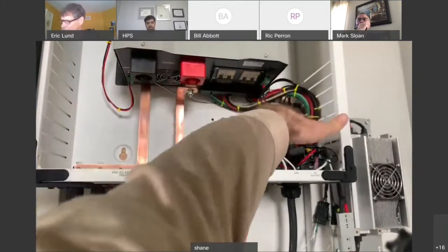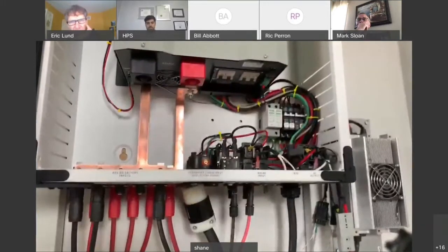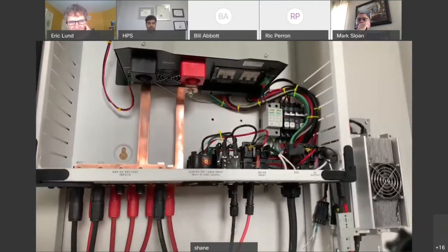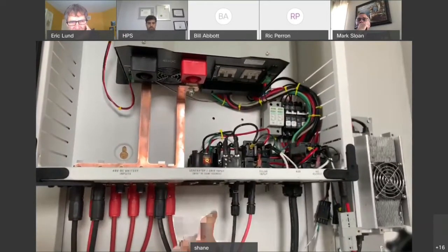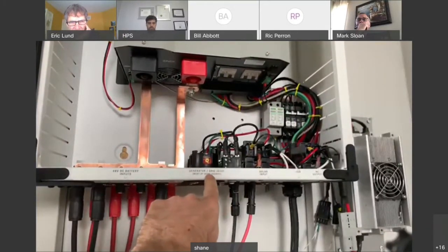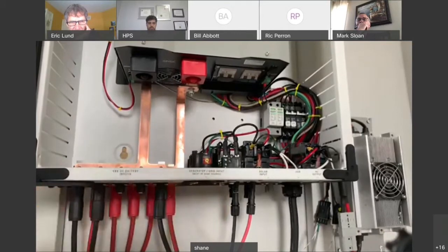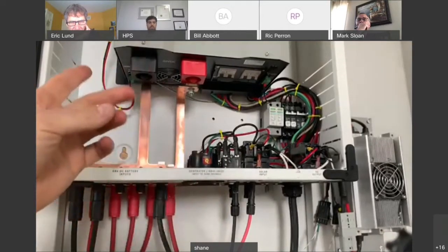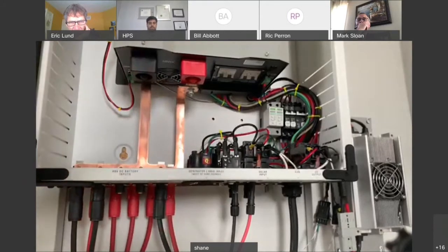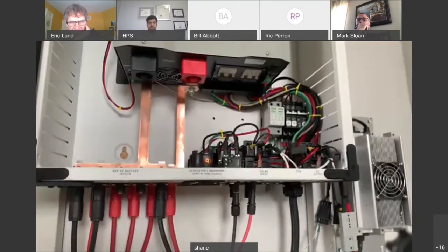Also, we have 2 contactors that are interlocked, and the reason being is because we have 2 inputs. And you can see here it says generator grid input must be from the same source. That's because if we put a 50 amp plug, which this could handle, for a 30 amp input and a 20 amp bypass, excuse me, it is very expensive and you have to run larger cable. And most of the time in an install, you're only going to get a 30 amp plug going into it from a generator. So that's why there's 2 of them.